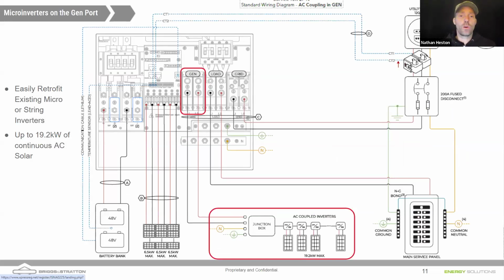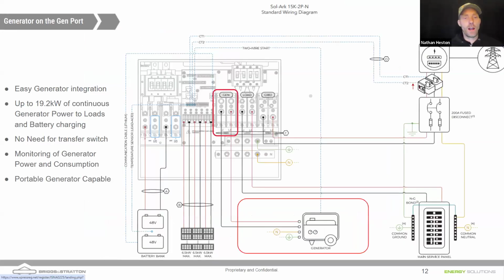You might have a micro inverter array on the roof, like an Enphase system up there. Solar Edge and Enphase are the typical AC coupled systems that we see. But we can use that generator port to bring in up to 19 kilowatts of AC coupled solar. And you could refer to Sol-Ark's guidelines about how much AC coupled solar versus DC solar. It's somewhat independent. The MPPTs are on the DC bus, and the AC coupled solar is coming in on the AC bus. But Sol-Ark gives some guidelines for how much solar you can bring in on the 15K.